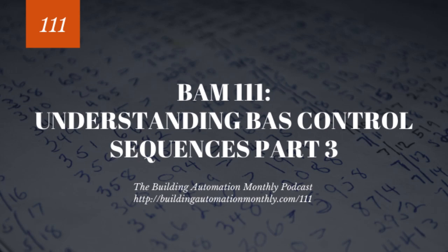Back to the 4 different loads, or ways of staging load. So the first way of staging load, as I mentioned, is this basic calculation of flow times delta T, right? And what you're doing here is you're looking at your GPM, and then you're looking at the difference between your supply and return temperature. That's delta T.